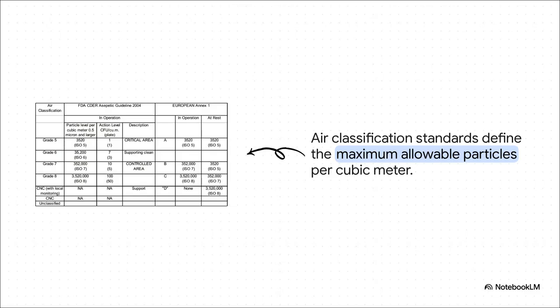And believe me, these rules are incredibly specific. Just take a look at this. In a top-tier grade 5 critical area, this is where the medicine is actually exposed to the air, the limit for particles of a certain size is only about 3,500 per cubic meter of air. Now compare that to a grade 8 support area, maybe like a hallway just outside. The limit there is over 3.5 million. That is 1,000 times dirtier, all within the same building. The difference is just staggering.